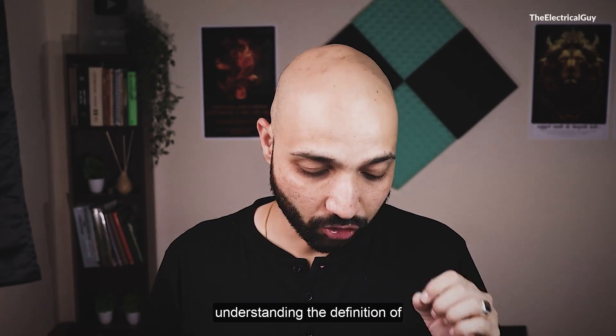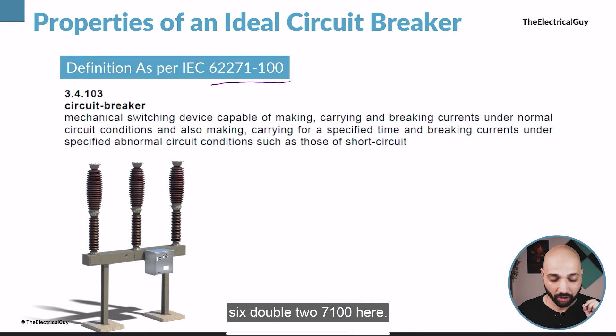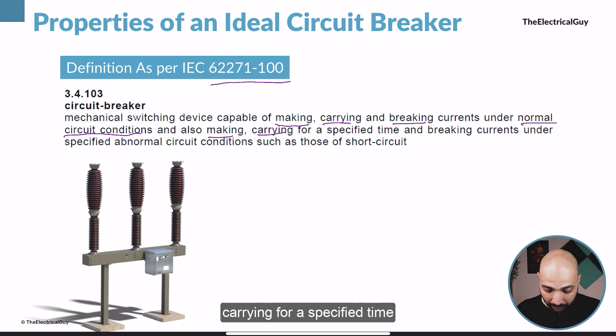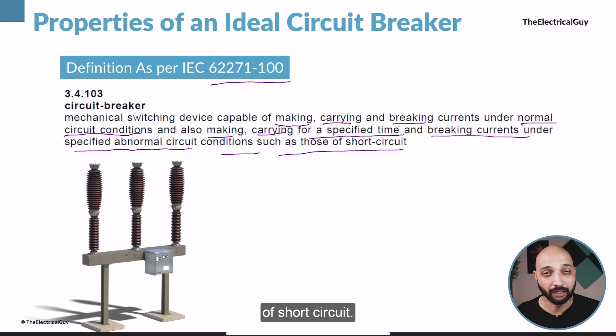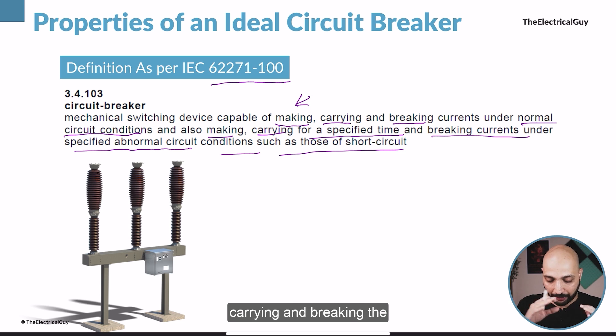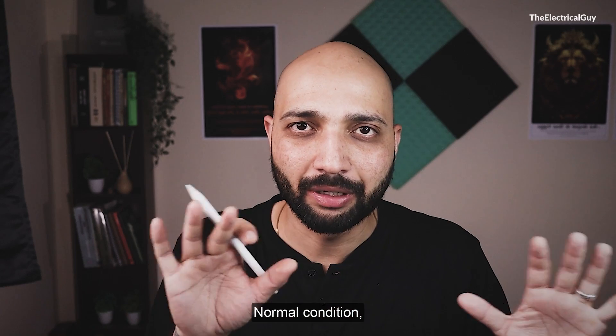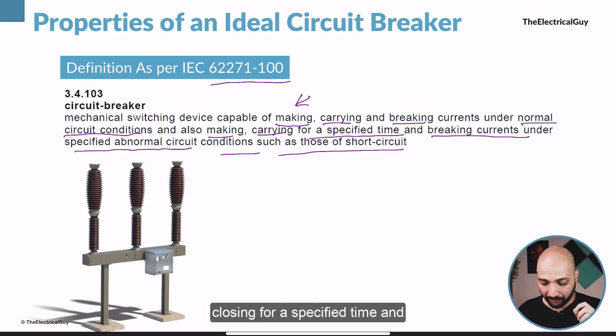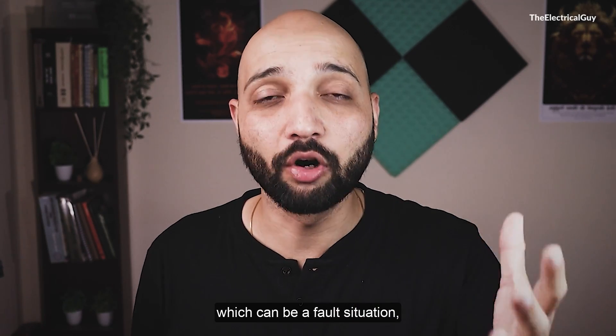Let us first start by understanding the definition of a circuit breaker given by IEC 62271-100. It states: a circuit breaker is a mechanical device capable of making, carrying, and breaking current under normal conditions, and also making and carrying for a specified time and breaking currents under abnormal conditions. So there are two parts: normal circuit conditions, and fault or abnormal conditions.